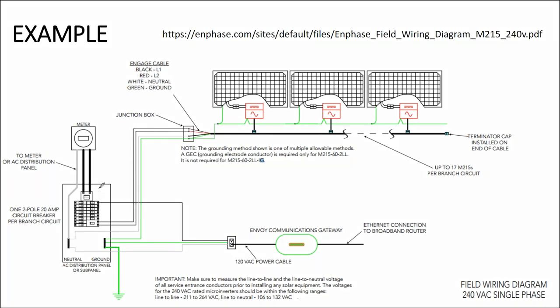And when you count up all the breakers on a service panel, you might get confused. You might count 300 amps worth of breakers on a service panel and then say, okay, what's up with this? I only have a 200 amp breaker. If I turn all the loads on in my house at the same time, can I flip that 200 amp breaker? The answer is yes.